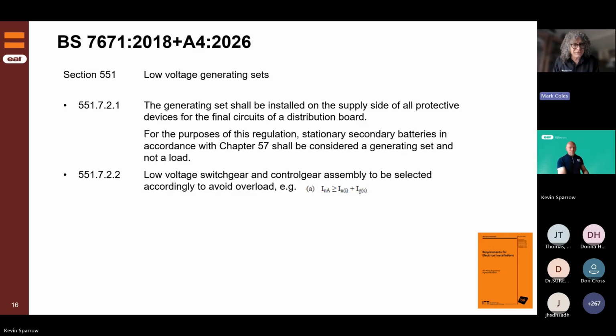The second part of this, 551.7.2.1, says: for the purposes of this regulation, stationary secondary batteries, in accordance with chapter 57, shall be considered a generating set and not a load. We'll look at chapter 57 in a moment. But what this is saying is that where you've got a battery and you're using it to supply the installation, you treat it as a generator. But when the battery is charging, it's not a generator at that point, it's a load - that's what that paragraph is getting at.